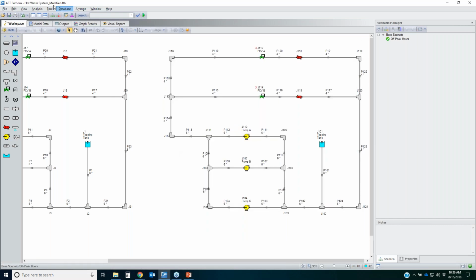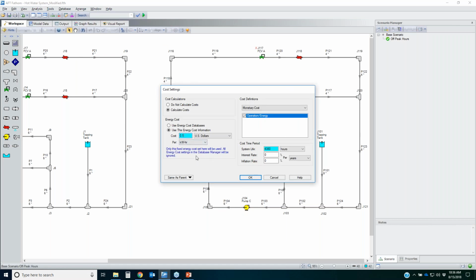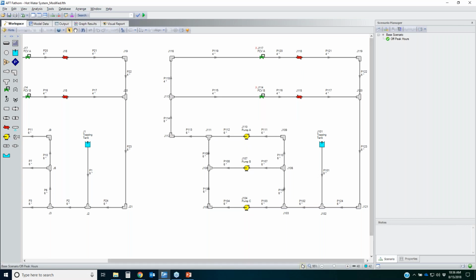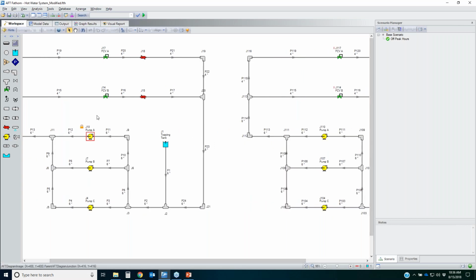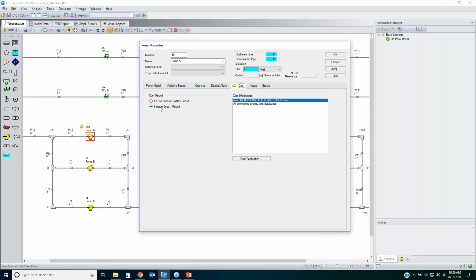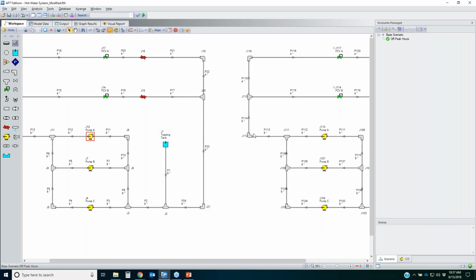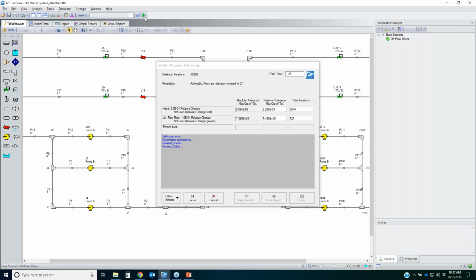The next thing I did was I set up my energy cost calculation. So I went to analysis, and then under cost calculation, I did pump energy only. And then for my cost settings, I'm assuming 10 cents per kilowatt hour. This is 12 hours a day, 365 days a year of off-peak operation. Once that was done, in order to get my cost report, I had to go into each pump on the cost tab, just include the cost for that object in the report. You could do this globally. So I selected all 6 pumps in the workspace and globally edited them to all include their costs in the report. So let's run this scenario here.